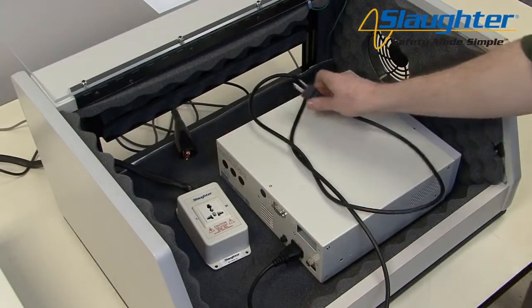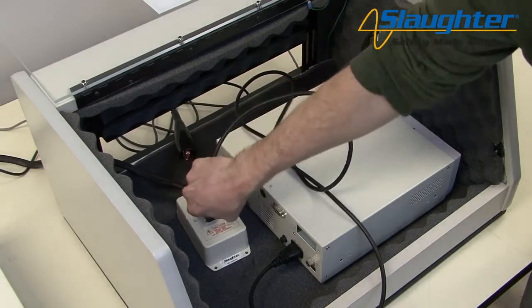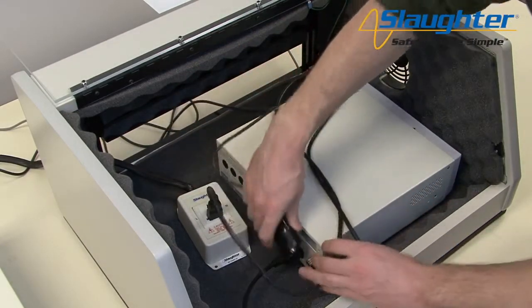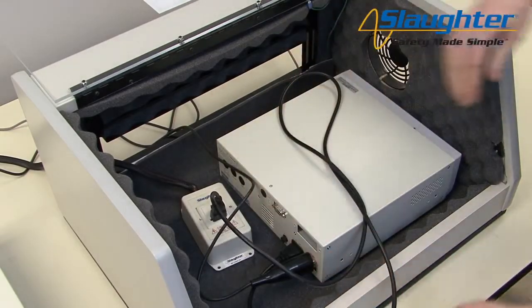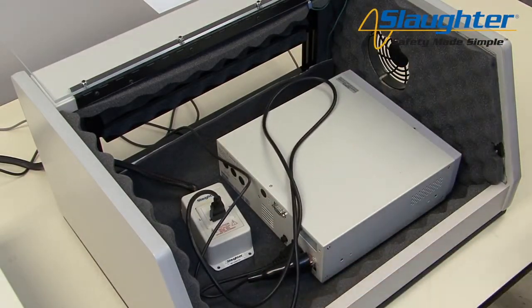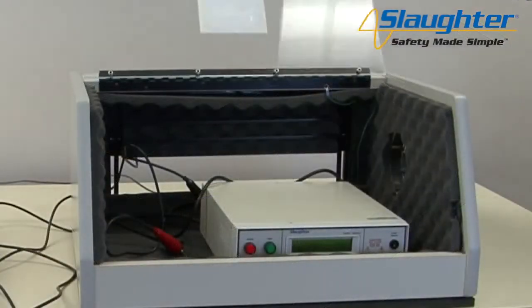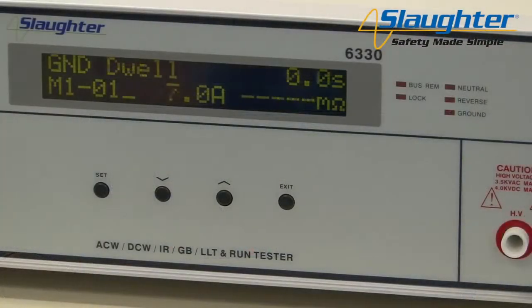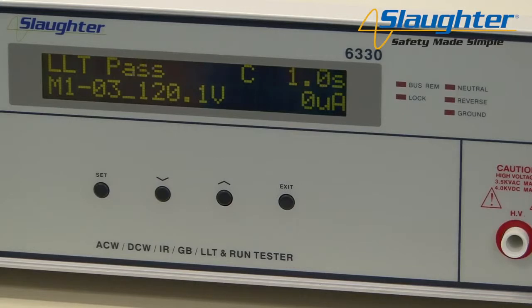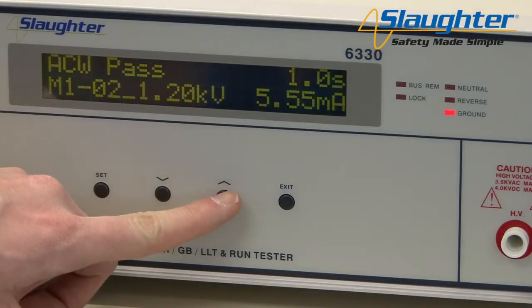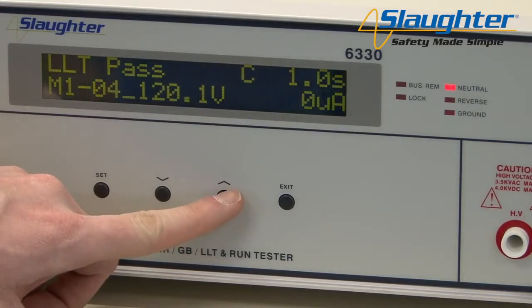To connect the DUT to the 6330, simply plug the 3-prong cord of the DUT into the adapter box. Connect the case lead to the chassis or to the dead metal on the DUT. Close the DUT enclosure door, stand back, and push the test button to run your test sequence. Notice that when running the line leakage test, the fault conditions LEDs illuminate to show you which fault conditions are occurring during each leakage test. Once your test sequence has completed, use the up and down arrow keys to review your results.